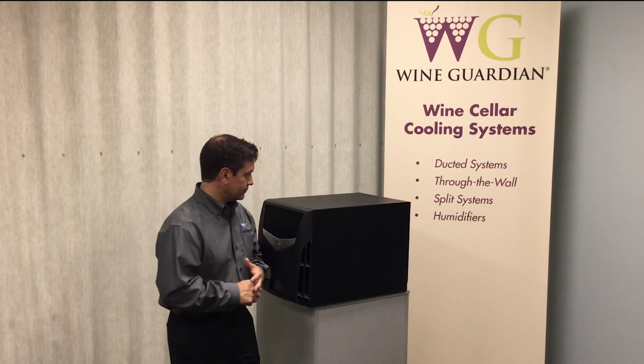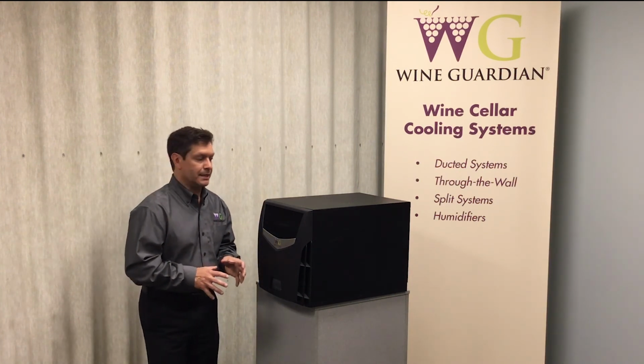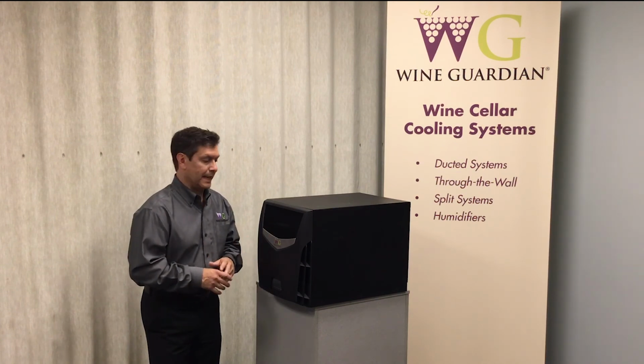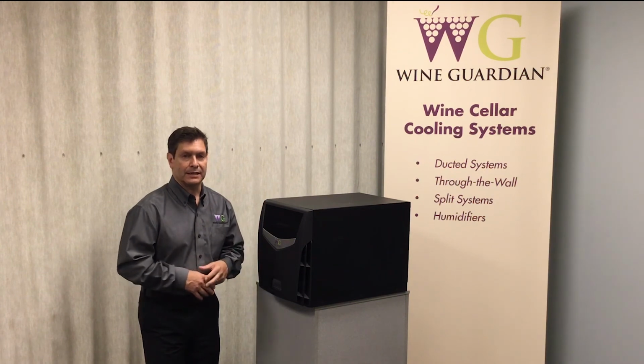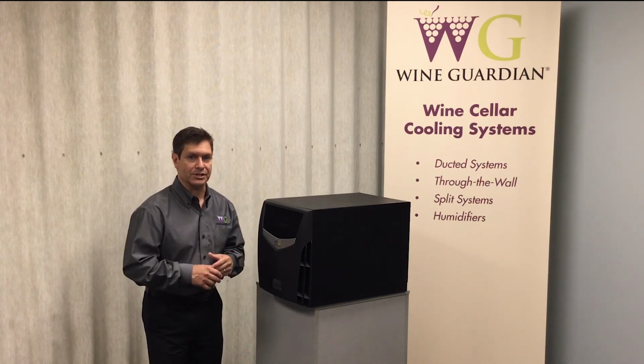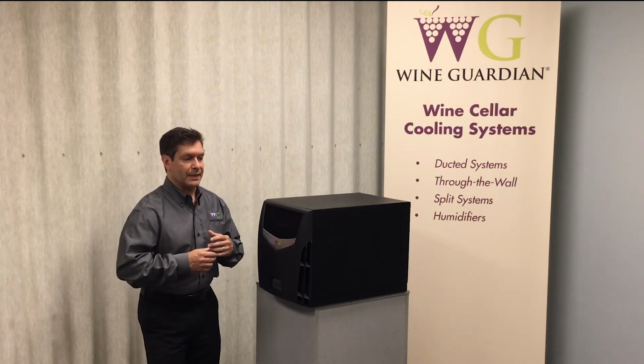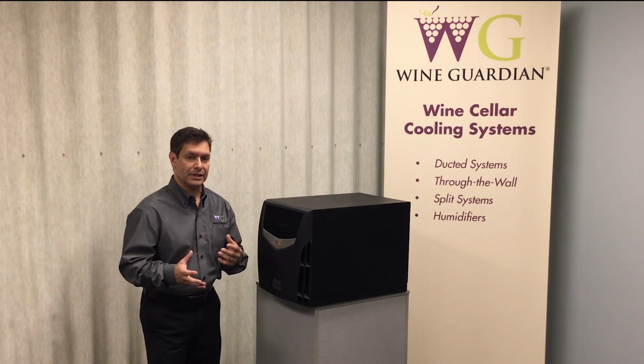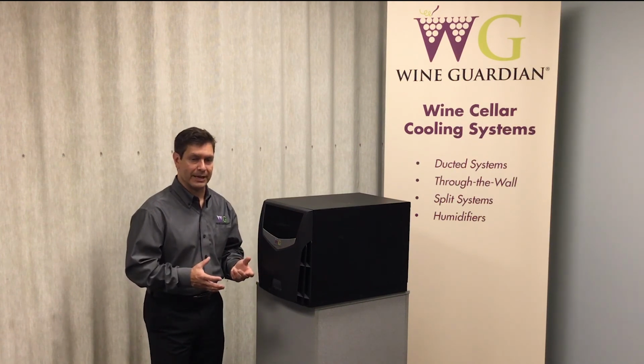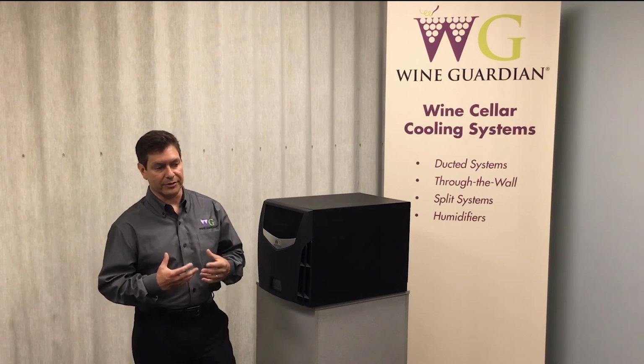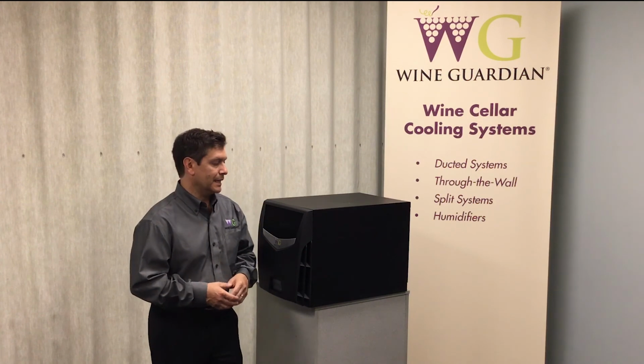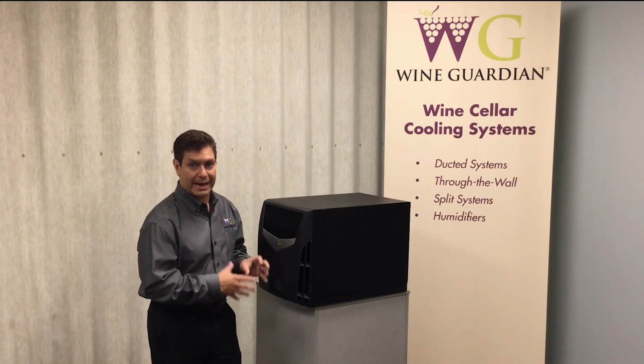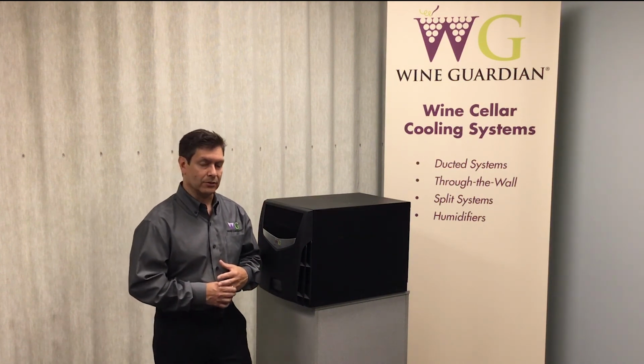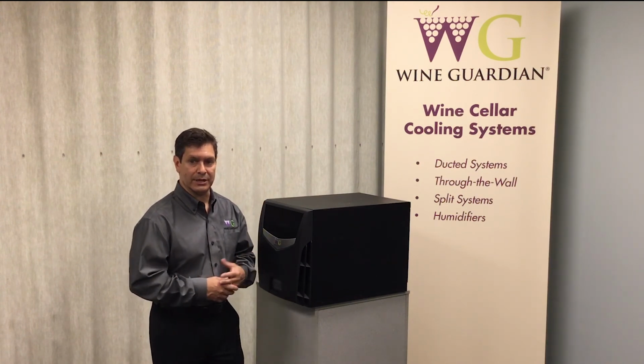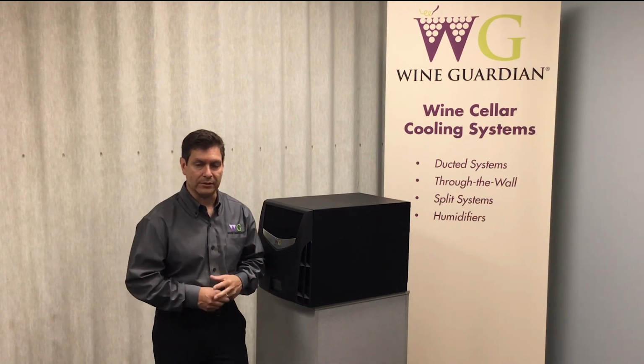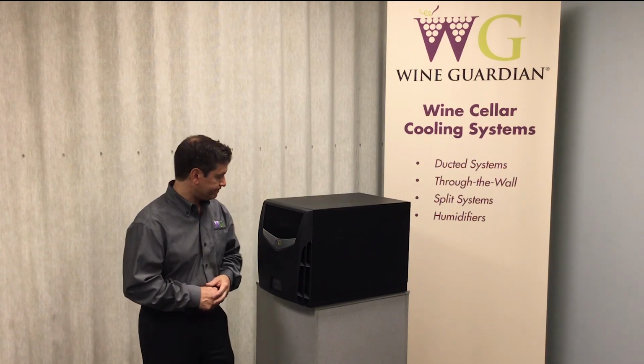Does the through-the-wall unit add humidity to the room? No, it doesn't. The through-the-wall unit is a cooling device only, and it's designed to maintain the humidity levels in the space anywhere from 50% RH up to 65% RH as far as its normal refrigeration cycle. So if your starting point for humidity is in that range, it should continue to maintain that level of humidity in the space. If you're lower than that and you're requiring that humidity level, which you should, be above 50% RH, this device does not have the ability to add that moisture back into the environment. You would need one of our standalone humidifiers to add that humidity. And as I mentioned, that is all controlled through the main control panel of our device if you choose to add a humidifier.